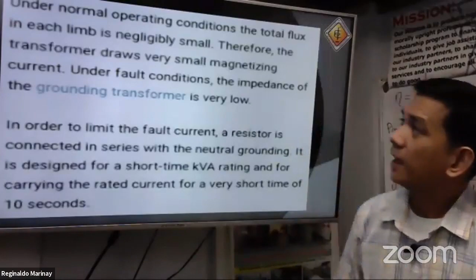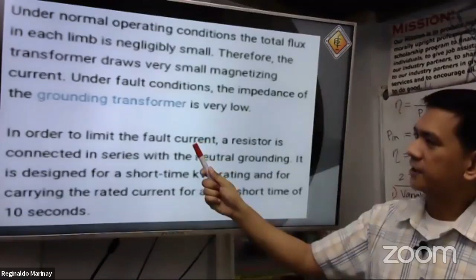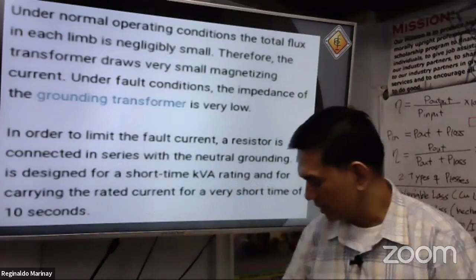Under normal operating condition, the total flux in each limb is negligibly small. Therefore, the transformer draws a very small magnetizing current. Under fault condition, the impedance of the grounding transformer is very low. So, when there is a fault here on this side, okay, the impedance of the grounding transformer is very low. In order to limit the fault current, a resistor is connected in series with the neutral grounding.